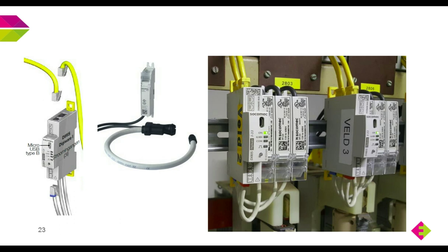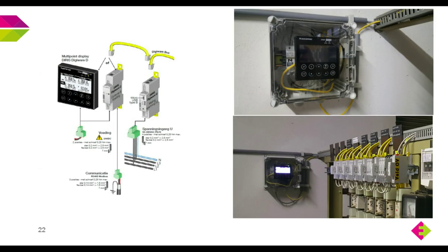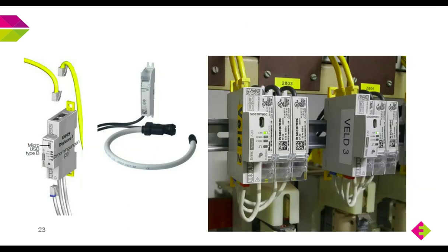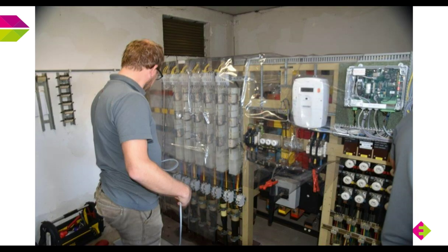You see, it is very flexible. You can put it on the cable, and after that you close it around the cable. There is a connector, and from this connector you go to a box where you can get all the information. And we install this in the stations in about 15 minutes. And in one of the stations we have also put the DALI box. We have here the Socomec installation at the upper side, and we have the Modbus connected to this Micronica box.